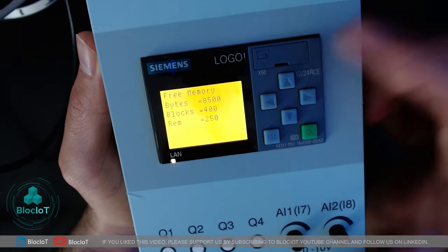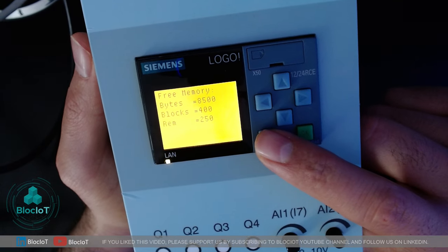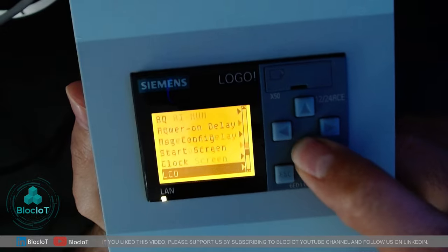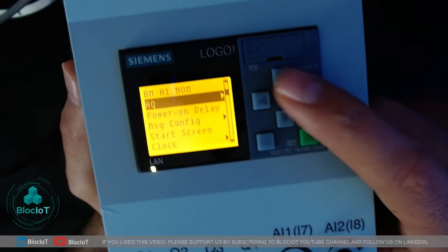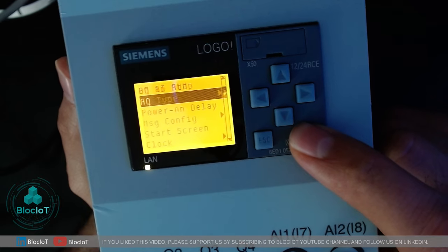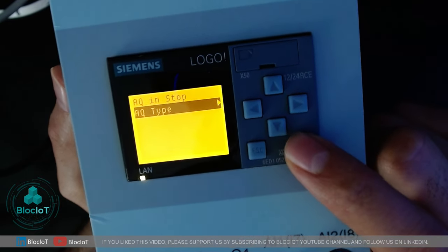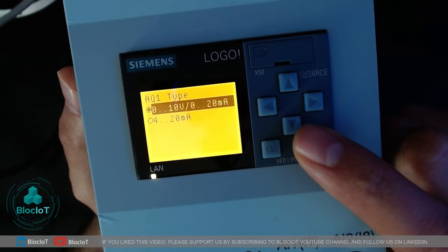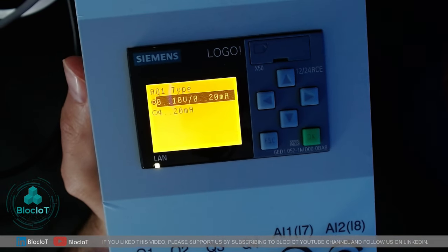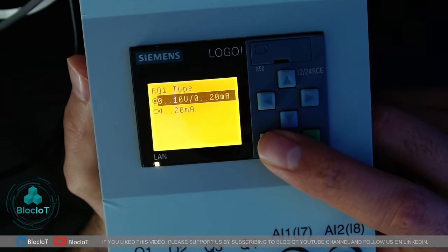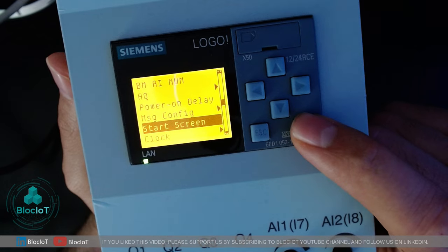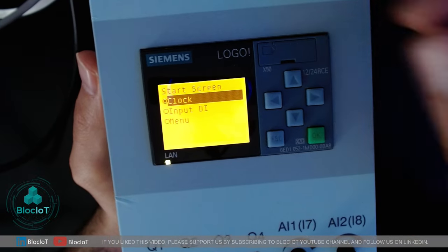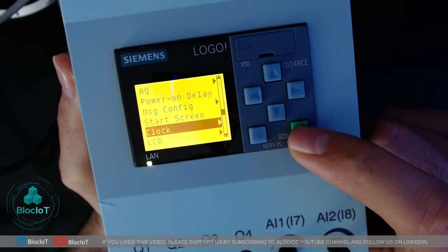The third option on the main menu is setup. Going into setup gives you many more options — for example, you can go to AQ (analog output) and adjust different parameters. You can define the AQ type: this Logo supports 0 to 10-volt DC or 4 to 20-milliamp DC, since some sensors give you 4-20mA and others give you 0-5 or 0-10 volts. Another setup option is the start screen — right now it's set to show the clock and date, but you can change it to show the status of your digital inputs instead.